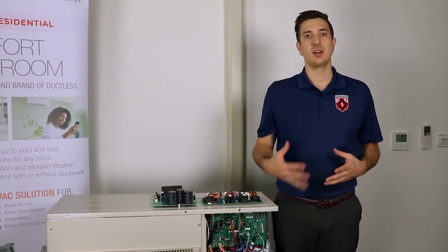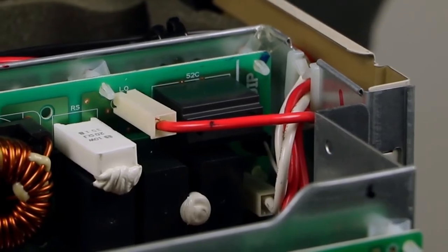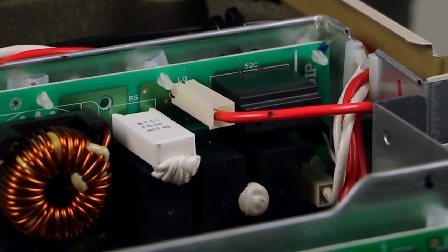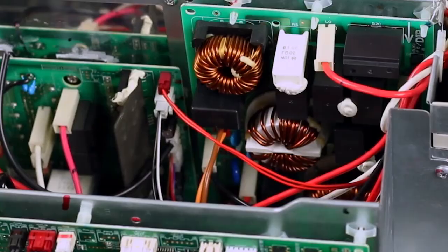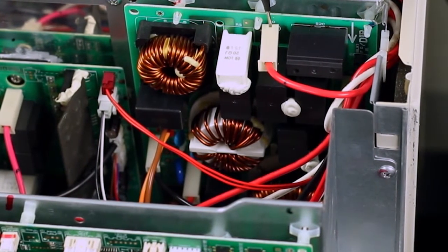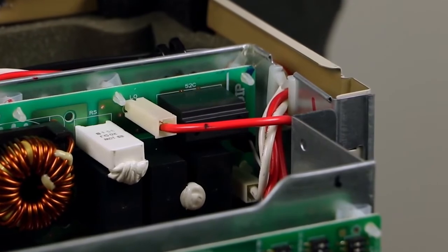Let's take a look at our system here and see how when the power board shorts, it ends up blowing the noise filter board. After we've verified that there's full power coming into the condenser — either 208 to 230 volts AC — we'll want to make sure that we have that same power leaving the noise filter board. Check your wiring schematic for the exact terminals. In this case, we're using terminals LO and NO. In my system, I still have a full 208 to 230 volts AC.